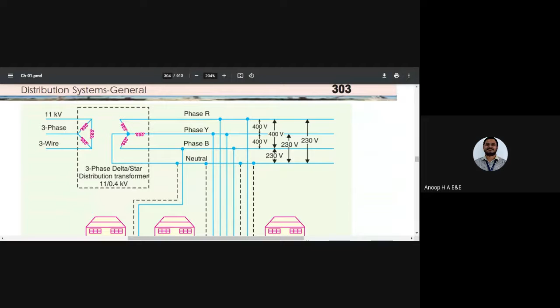The other side, where high power is to be drawn, is at 11 kilovolt, so the voltage is high, and it is stepped down to 0.4 kilovolt, which is 440 volts. Are you getting it? So this side is the delta connection, and this side is the star connection. As you can see, the neutral point is extended over here and directly connected to the household. That is the reason why we prefer delta connection for the high voltage and star connection for the low voltage appliances.